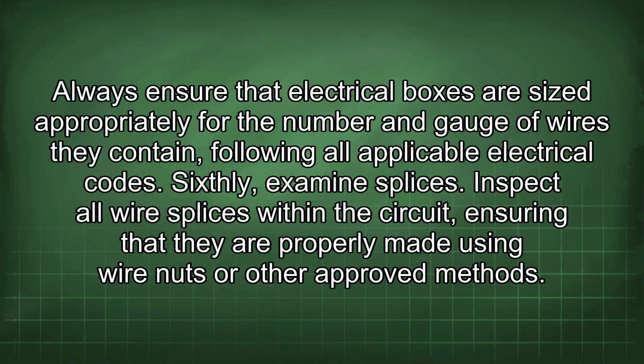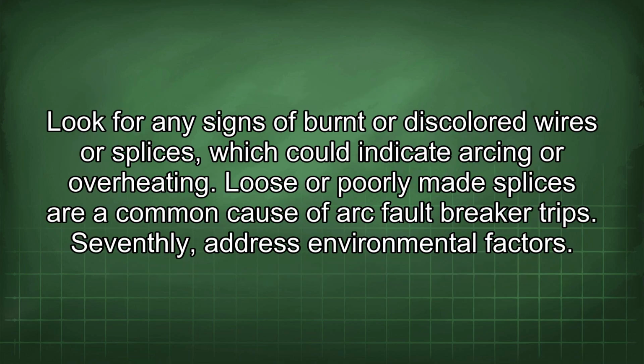Sixthly, examine splices. Inspect all wire splices within the circuit, ensuring that they are properly made using wire nuts or other approved methods. Look for any signs of burnt or discolored wires or splices, which could indicate arcing or overheating. Loose or poorly made splices are a common cause of arc fault breaker trips.